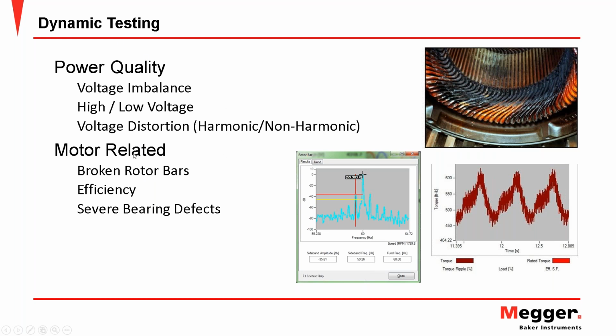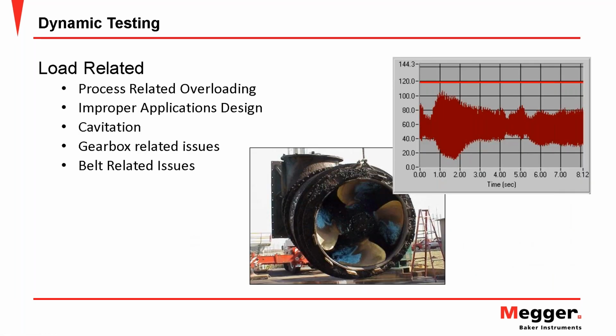Dynamic testing also gives us some clarity on rotor bar health, especially in our induction motors, how efficiently our motors are operating, and of course any other kind of mechanical defects like severe bearing faults. Okay, and we'd be remiss if we didn't talk about dynamic testing to point out that torque is telling us directly what's going on with the load: process overloads, improper application, cavitation, which is what's shown here. We can just qualitatively see that that's a problem. Gearbox related issues, belt related issues, and the list goes on and on.